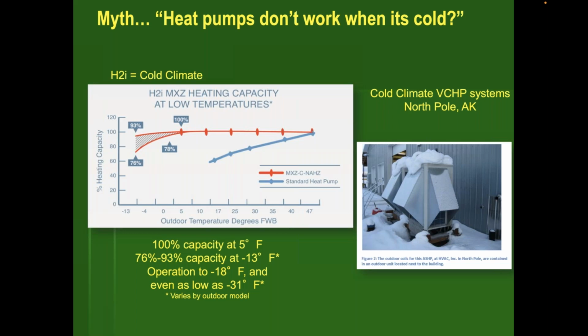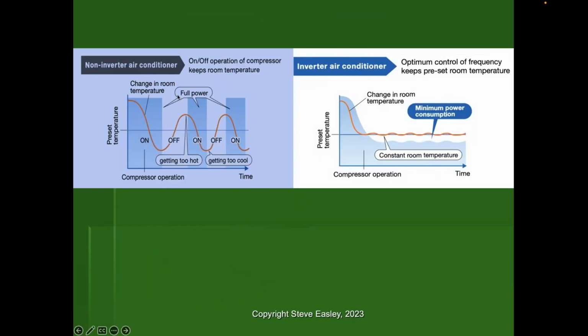In other words, remember the efficiency of the HSPF2 or SEER2 doesn't have anything to do with anything other than the efficiency of the equipment. It doesn't mean that the installed efficiency is going to improve that much, because even if I buy a traditional piece of equipment, like a standard heat pump with a big single speed compressor, it may have a high SEER rating or a high HSPF rating. And this is an important distinction, but that doesn't mean it has the capacity to be variable speed. So you're still going to have these big temperature swings, you're still going to have these big amp draws, and you're going to have more power consumption, even though it's more efficient than its counterpart. The beauty of the inverter-driven technology is that you can vary the speed of the compressor based on the real load.